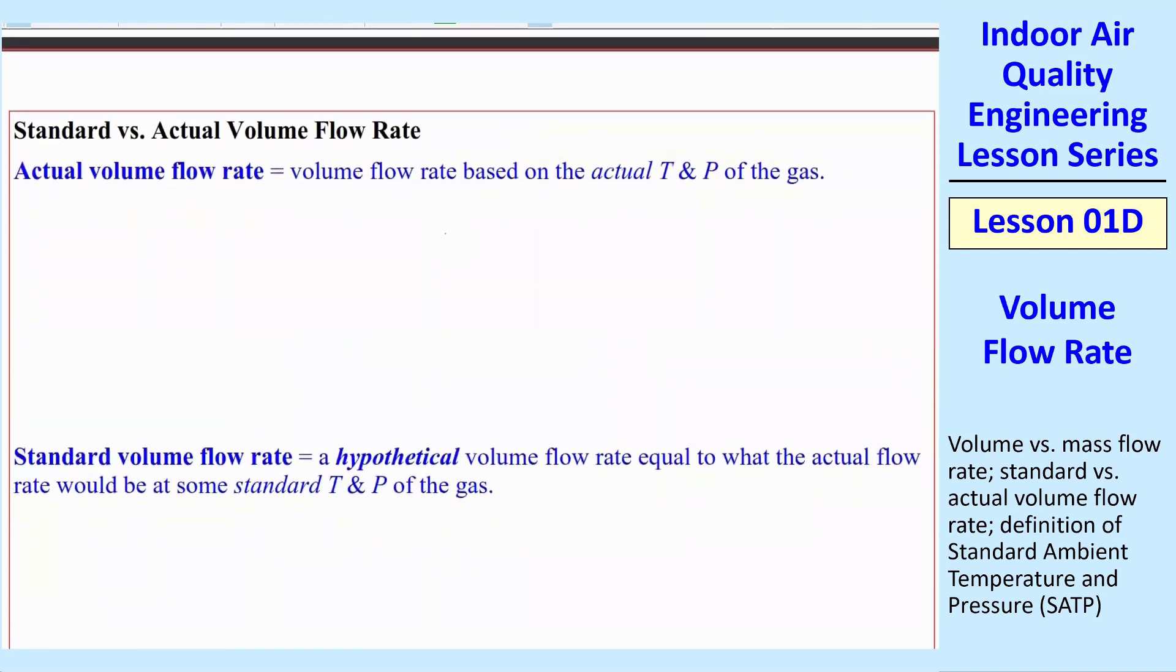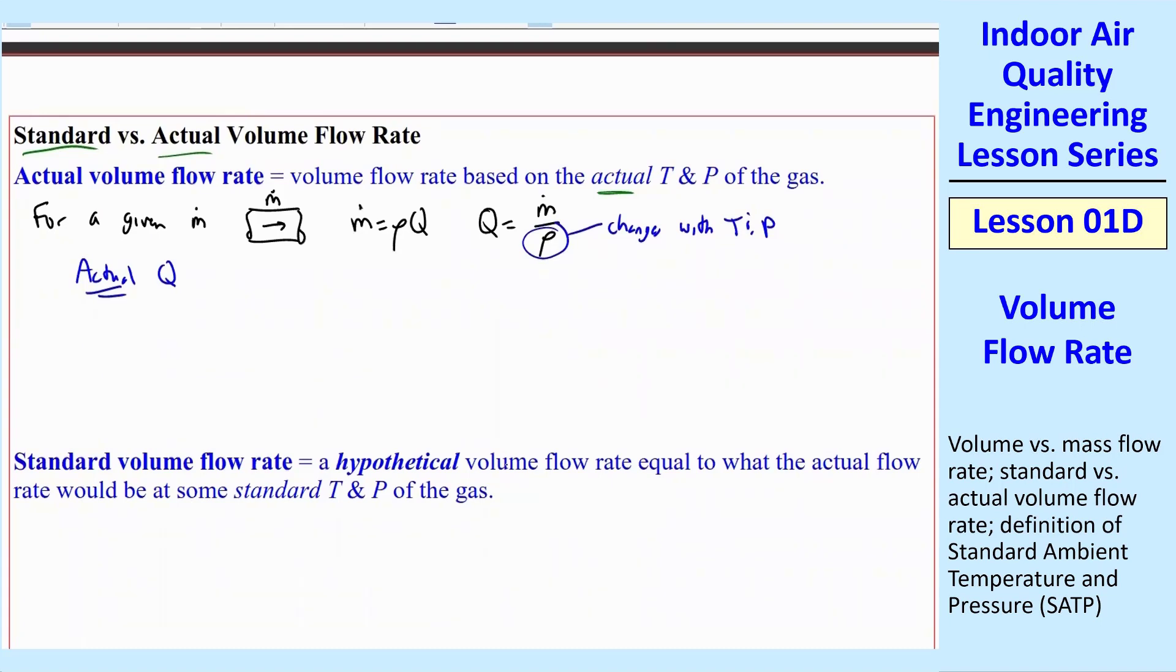There's a difference between what we call standard and actual volume flow rate. So I want to make sure that you understand that difference. By definition, actual volume flow rate is the volume flow rate based on the actual, as the name implies, actual temperature and pressure of the gas. So basically for a given M dot through the duct. This may be a round duct or a rectangular duct, but there's some M dot flowing through there. So M dot is rho times Q, and Q is then M dot over rho.